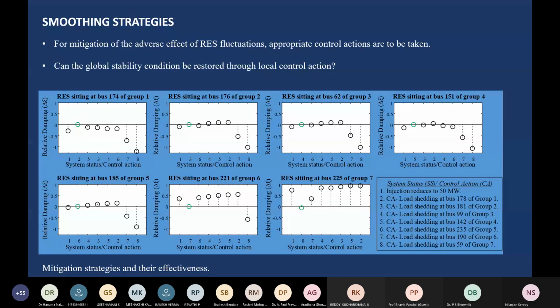So if I reduce the injection by 50 megawatts in group 1, which is the top left hand graph, the damping of the most critical mode reduces. To restore the damping back to its original value, I need to take control action number 2, which is load shedding at group 1. So if I do the load shedding in the same group where the injection has been reduced, then the damping is restored back to 0. Similarly, in the graph for group 3, the green dot corresponds to control action number 4, which is load shedding in group 3. Similarly, for the renewable energy siting for group 4, the control action that will restore the damping back to 0 is control action number 5, which is load shedding at group 4.